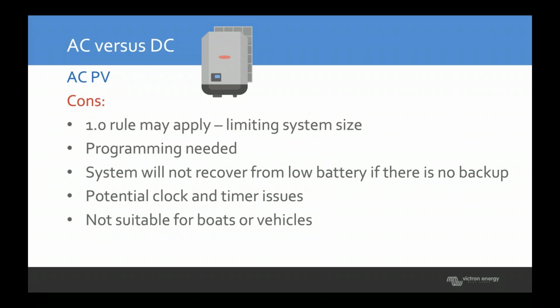It'll give as much PV power as it can. But as the batteries begin to fill up, or they want to reduce the amount of charge in an absorption phase or something like that, then the frequency will increase. As the frequency goes up, let's say to 51 Hertz, anything that uses that frequency as a timer, which can be old clocks and things like that, will also speed up. So if the clock in the house is using that 50 Hertz frequency to set itself, it can begin to go faster than you'd expect for normal time. It's not a huge issue, but it's something to be aware of.